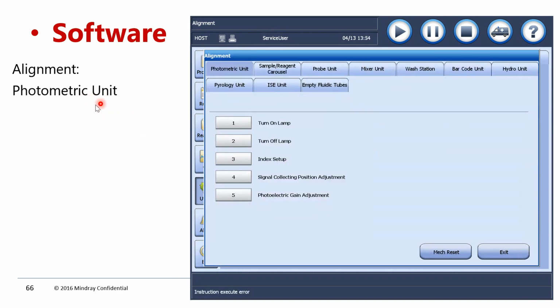And alignment of the photometric unit. Whenever you are doing alignment of the photometric unit, there is an option called signal collecting position. The cuvette width is 5 mm, right? What we are using is spot photometry, meaning the cuvette comes in front of the lamp or photometry unit. We need to take the measurement at the center of the cuvette, not the left side or right side. So we call it the signal collecting position. We can adjust the sensor based on that, so that we collect the signal at the right center position.